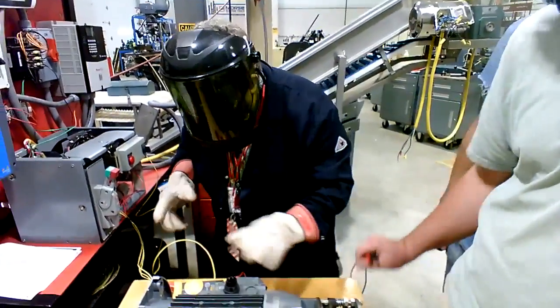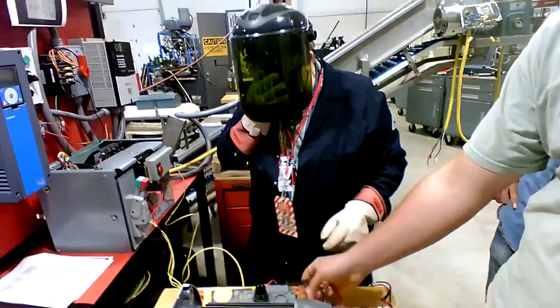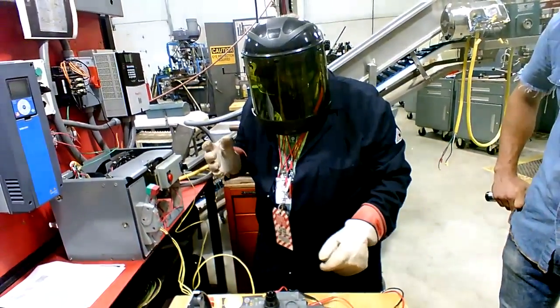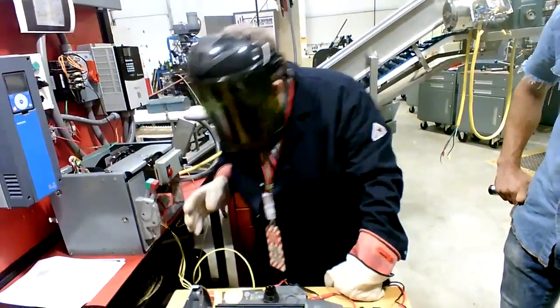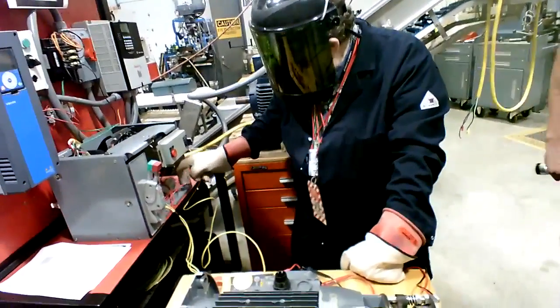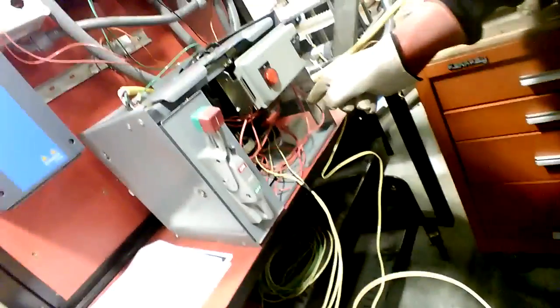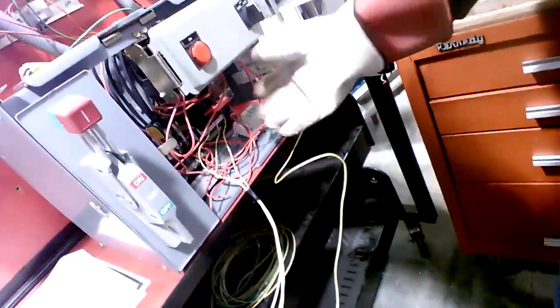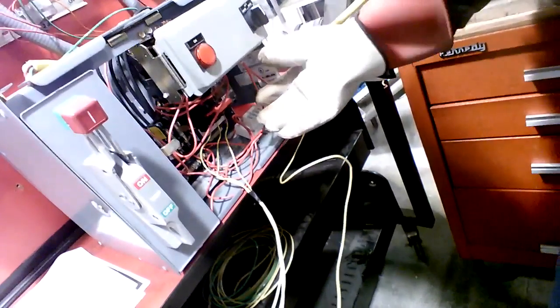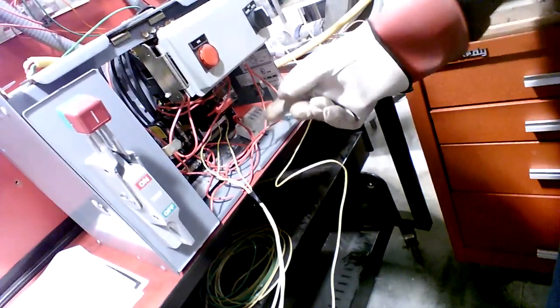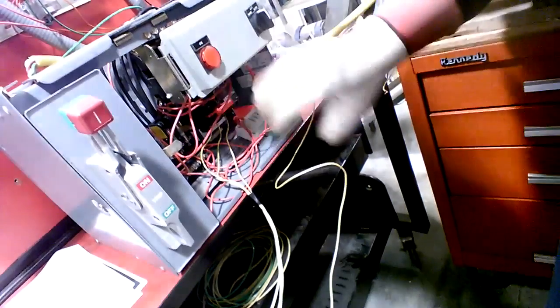Now, for instance, I'm going to give you two scenarios that will point in the direction of what could be a problem. Electrical. Let's say you went in and checked the voltage phase to phase, and they were similar like they are now. And if you check phase to ground, they are very similar, okay? They're somewhere in that range of what's nominal, you know, 277 to ground and 480 leg to leg. And that stuff looks normal.